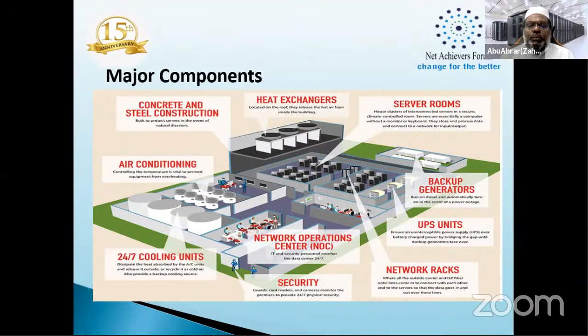So the power UPS system, uninterruptible power supply system, is the main component of the data center next to the room. There are different types of UPS systems: normal UPS, redundant UPS, and nowadays modular UPS is in place. For example, if we need 100 kVA, 200 kVA, or 500 kVA UPS, you have to have a minimum of 2, for redundancy purposes.